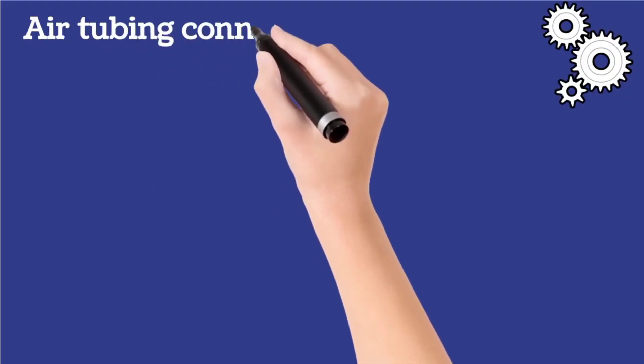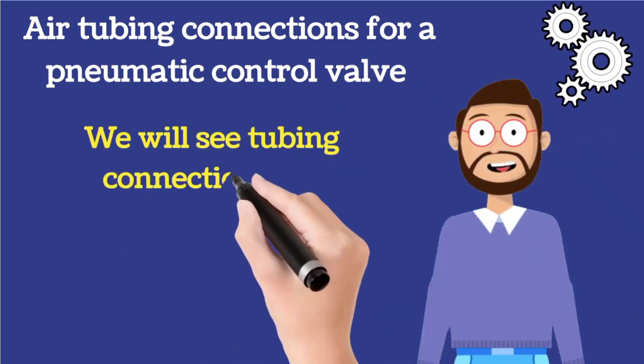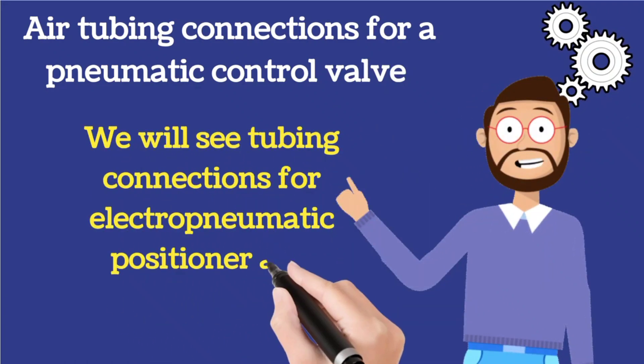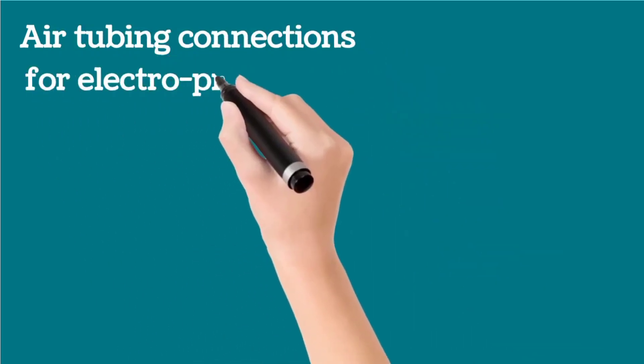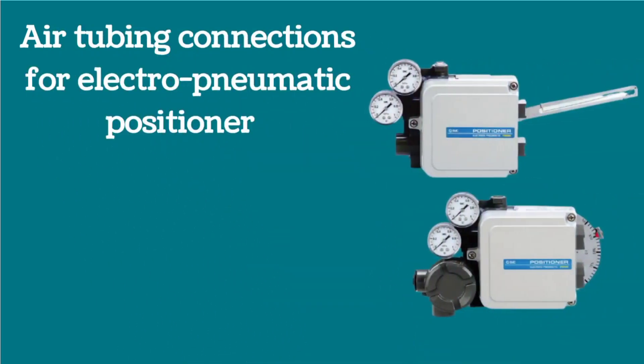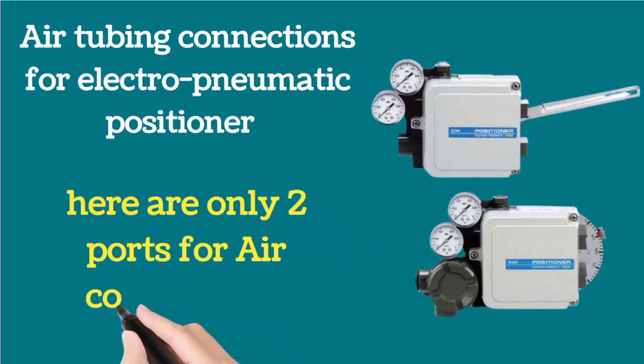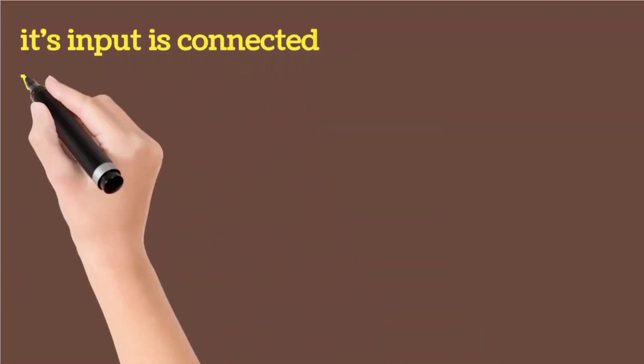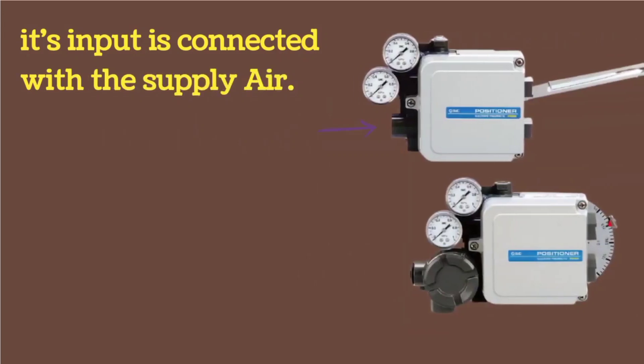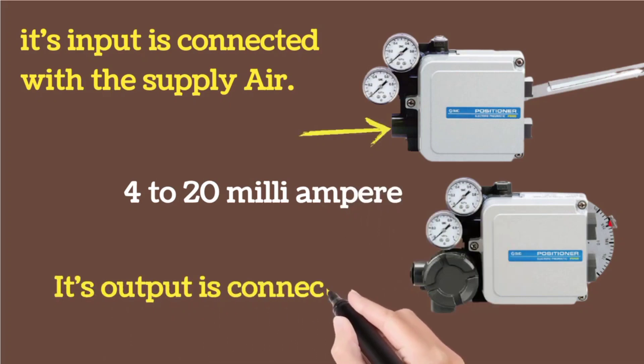Let me explain air tubing connections for a pneumatic control valve. We will discuss tubing connections for the electropneumatic positioner and the pneumatic positioner. First, I will explain air tubing connections for the electropneumatic positioner. Tubing connections are very easy for this positioner. This positioner has only two ports for air connections. Its input is connected with supply air. A 4 to 20 milliampere signal is provided here as shown in the image, and its output is connected with the control valve.